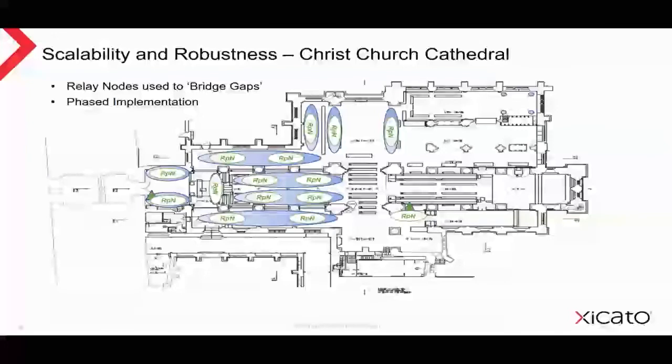However, this needs to be balanced against having too many repeaters, which can cause an overload of messages entering the system. As a rule of thumb, up to 200 messages per second can be sent within a given space before the network performance begins to suffer.